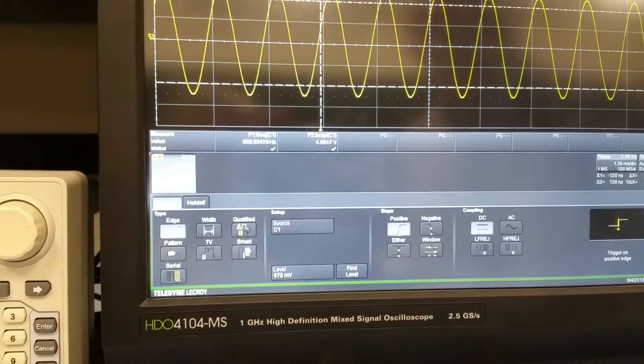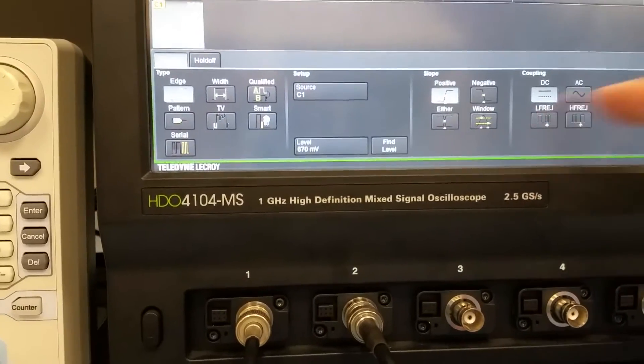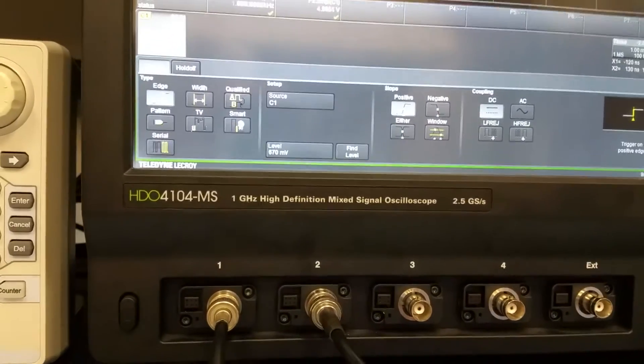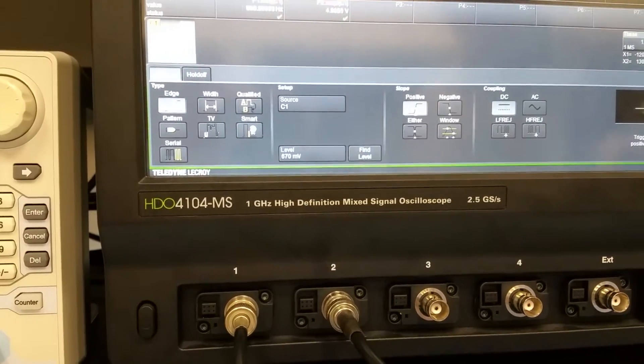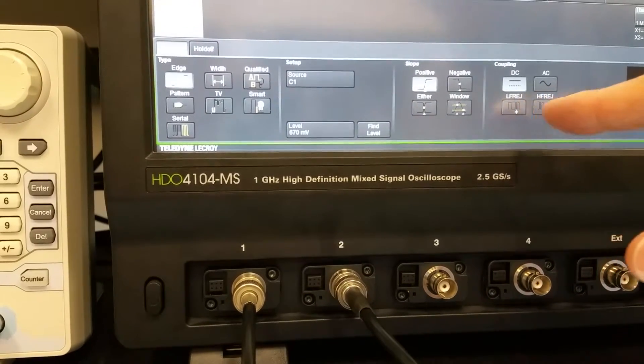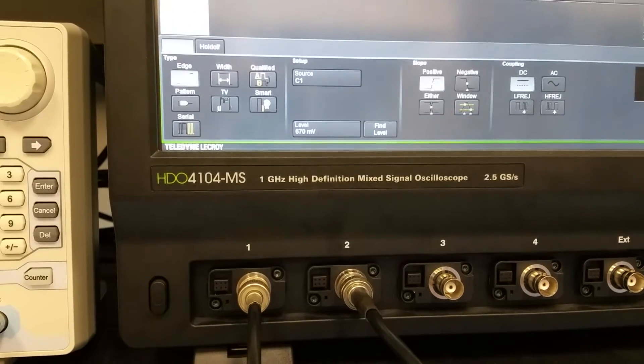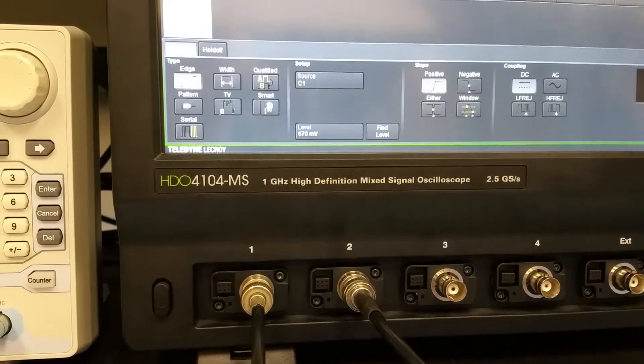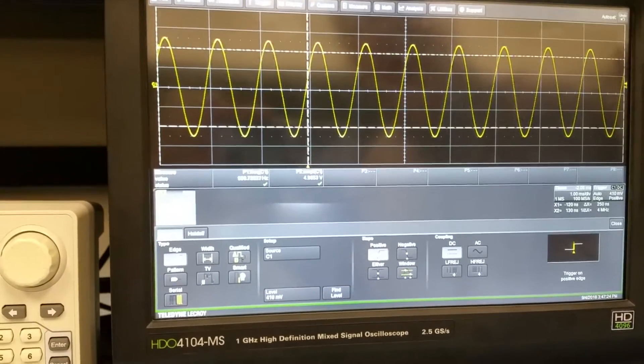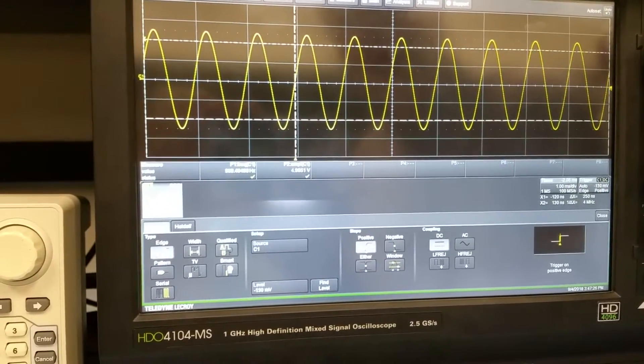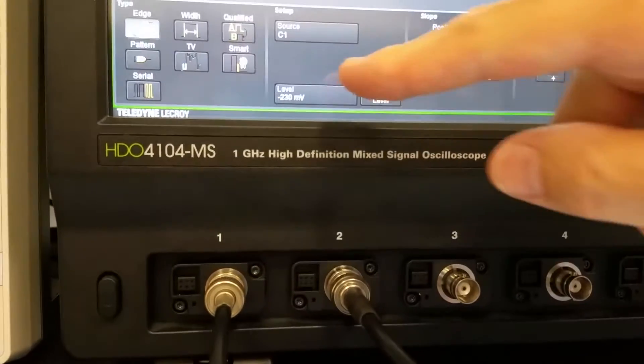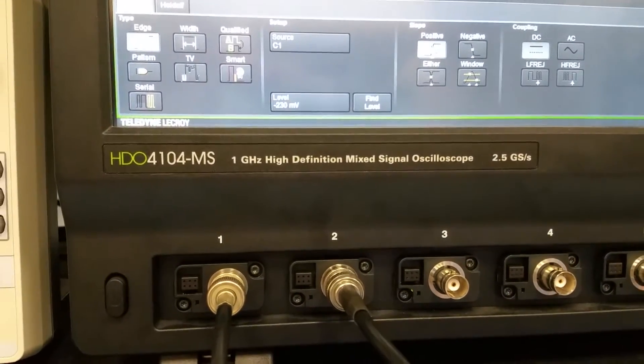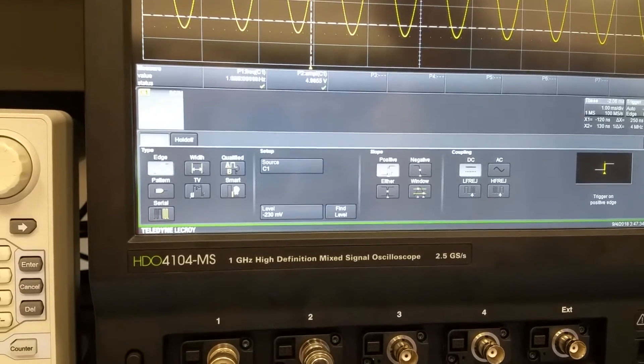Okay, there's some more things that we can do. We can choose filters. If it's a noisy signal, it might have trouble finding these points. So you can put a low frequency reject or a high frequency reject to help get a cleaner signal to do that. And also, you might notice that as we change the level, the triggering level, and this is moving, which we expect, that also shows up in this box. So you can set the trigger level by entering numbers if you want to do that.